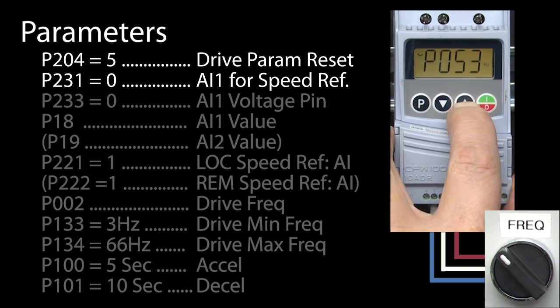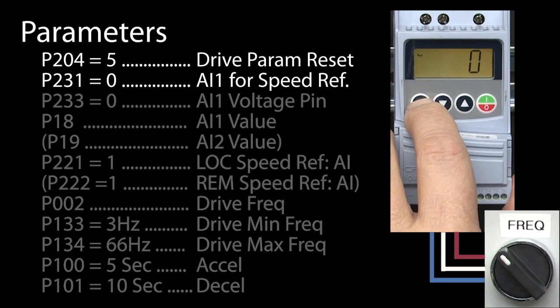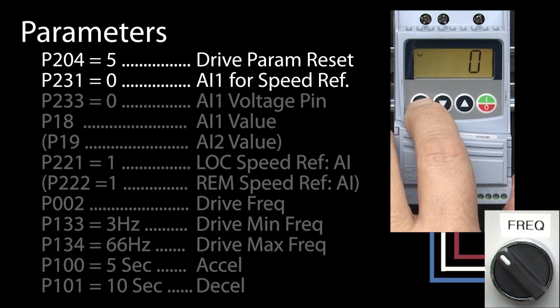First, we need to go to parameter 231 to tell the drive we're using analog input 1 as a speed reference. According to the manual, we need a zero for that. And as it turns out, that's a default, so we're good to go there.